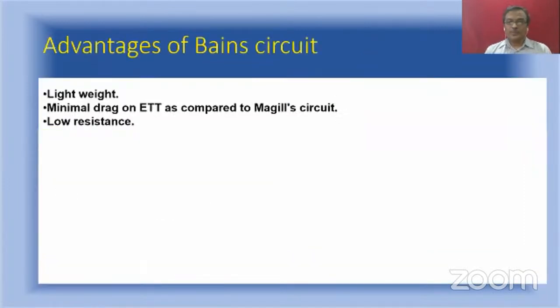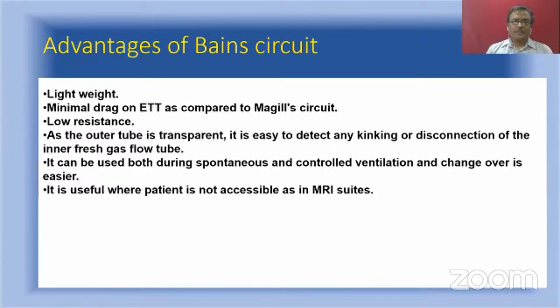Now, what are the advantages of the Bain circuit? It is lightweight, so you can move around. With the Magill circuit, the APL valve is heavier, but with Bain, it is light, and resistance is very low. And since the outer tube is transparent, you can see the inner tube clearly. And it is easy to move between controlled ventilation and spontaneous ventilation. And it is a very useful circuit in MRI suites.